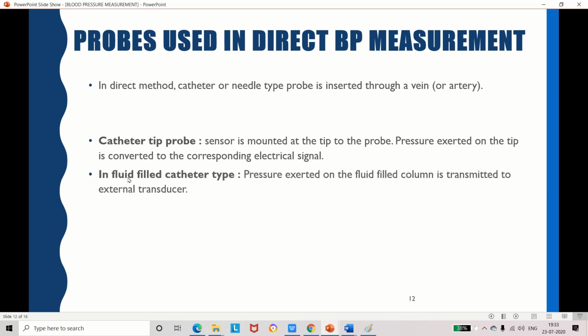Now the second method is the fluid filled catheter type. So this catheter system is filled with fluid, and by using this we can measure the blood pressure. Here we are having a pressure transducer. The pressure value will be converted into an electrical signal and we can measure that.